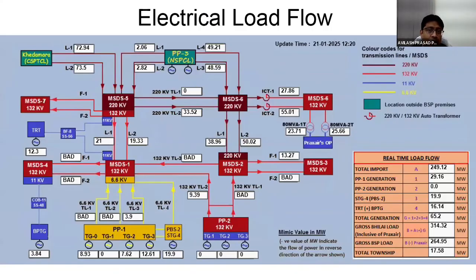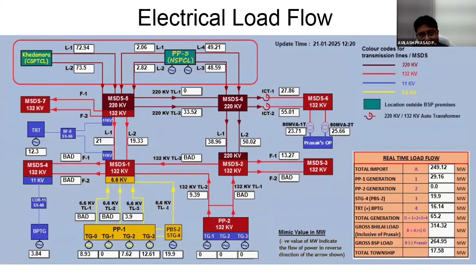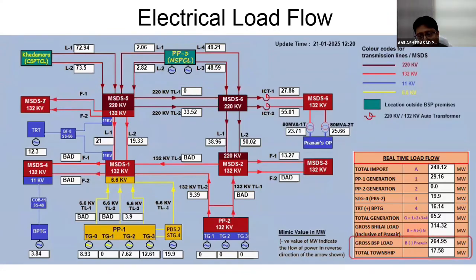Now on the screen is the electrical load flow of Bhilai steel plant. We will cover, one by one, what is relevant to us. First, the area which is blinking is Chhattisgarh State Electricity Power, from which we are connected with the grid. We are drawing power from there, and also connected is the NTPC SAIL joint venture PP3. This is a 220 kV line. Our gross BSP load is around 265 megawatt, and our township load is around 17.5 megawatt. The area blinking is showing the parameter.